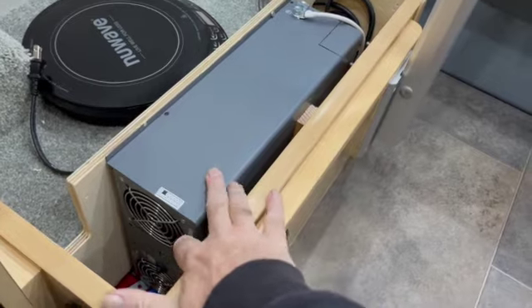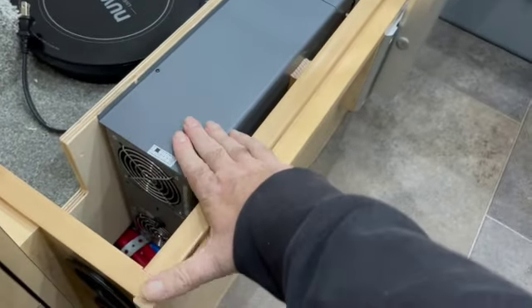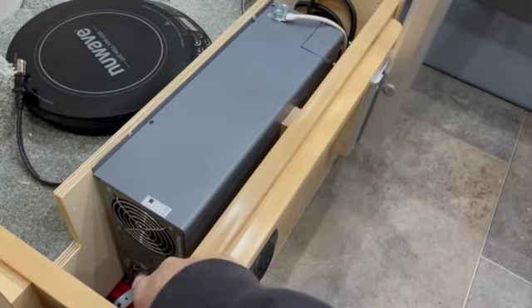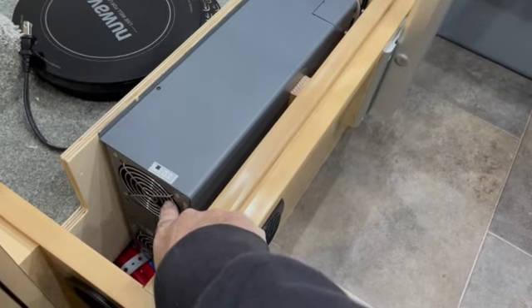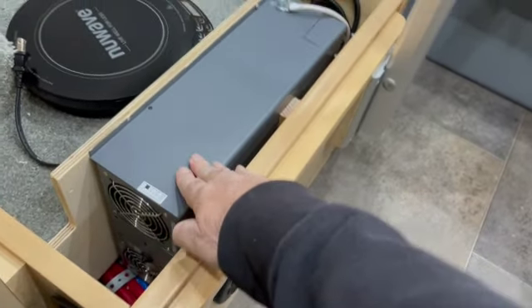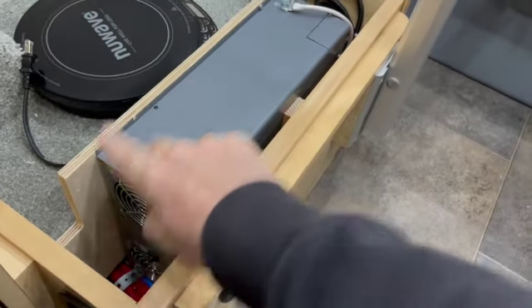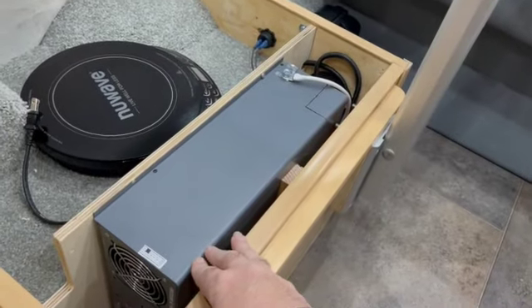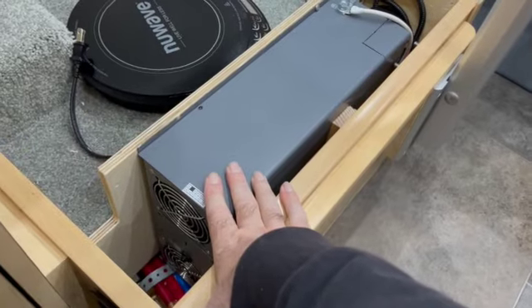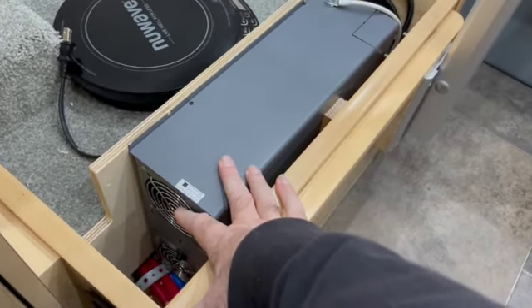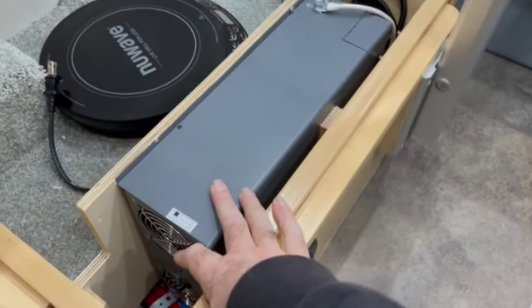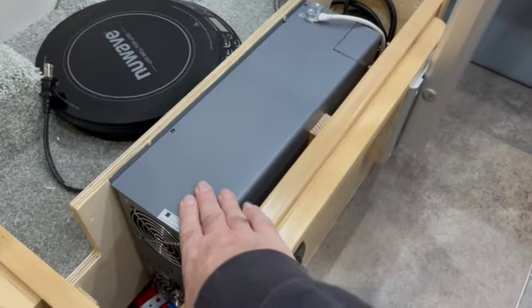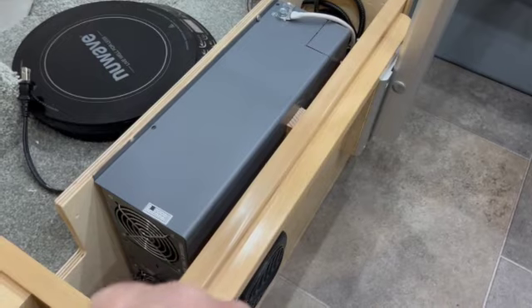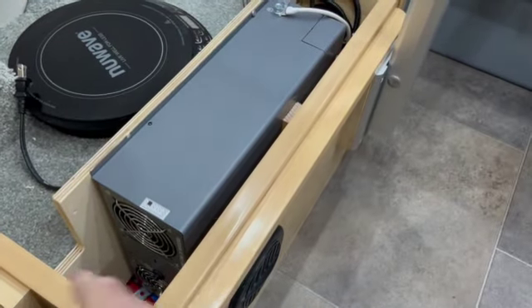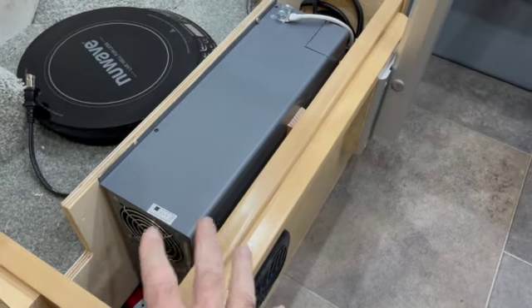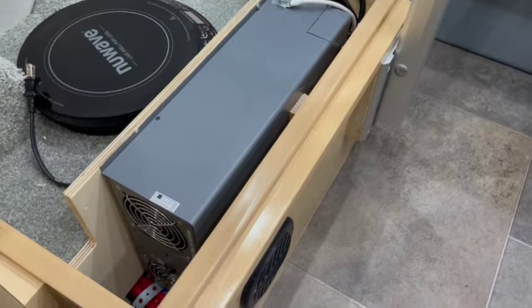With this inverter, whether you put a 3,000 or 2,000 watt inverter in, these Xantrex inverters have two very high velocity fans in the back, and this is what cools the inverter. So you're going to have a lot of air sucking in here, and then it comes out at the other end. And I noticed that the fans would run whenever you plug it in to charge, and then it'll cycle on and off during the day based on the load that you have as this warms up. I have an infrared thermometer that I've been checking the temperature with. So as I hear it run, I'll pop this lid and shoot the fans with the infrared and see what the temperature is. I can see the temperature of this cavity as well.